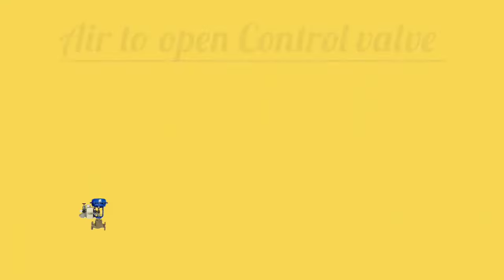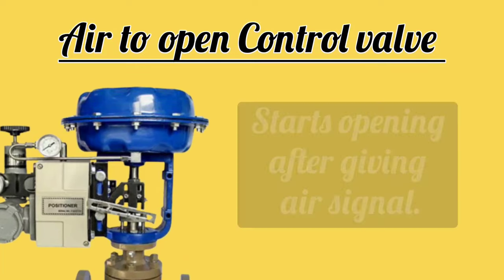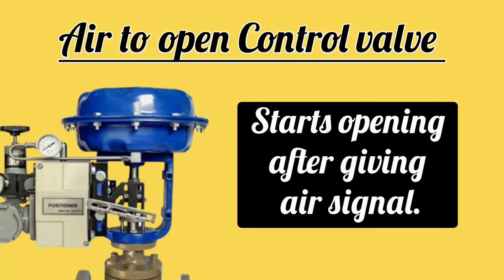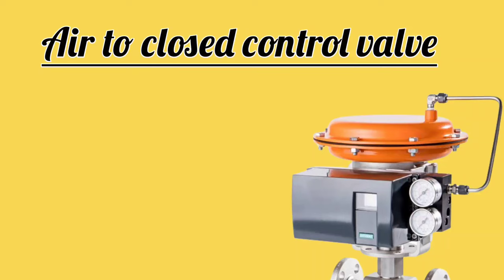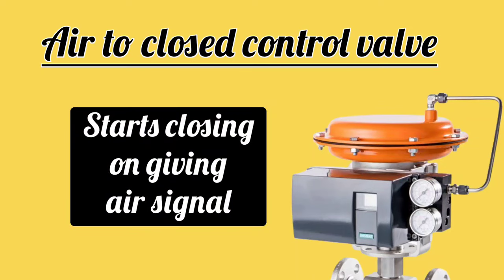See friends, the air-to-open control valve starts opening after giving an air signal. In this control valve, air is supplied from the bottom of the diaphragm. And the air-to-closed control valve starts closing on giving an air signal. In this control valve, the air signal is supplied above the diaphragm.